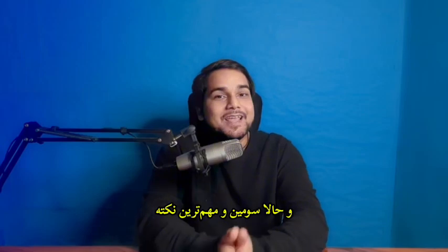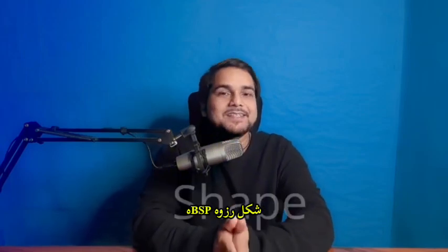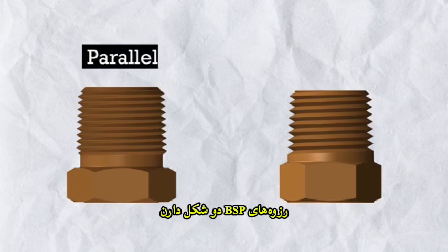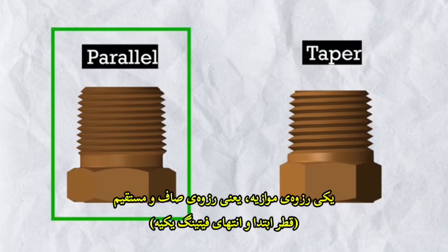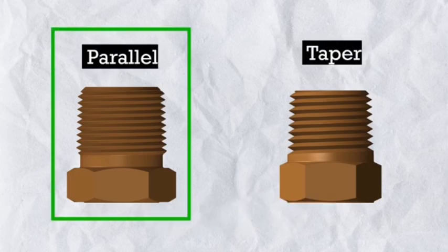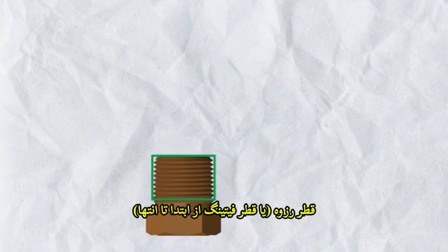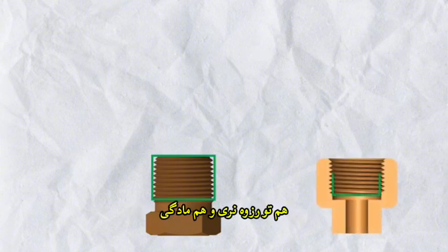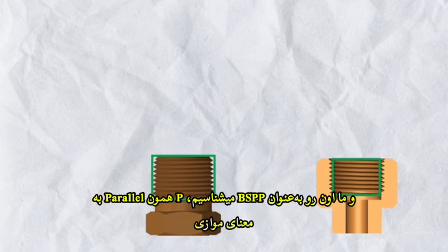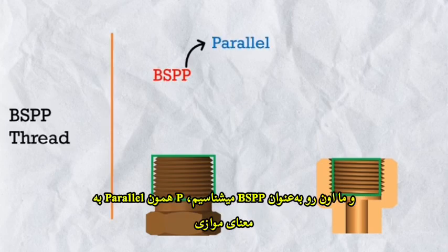And now the third and most important thing is the shape of BSP thread. BSP threads come in two shapes. One is parallel thread, means a straight thread. The diameter of the thread will stay constant throughout the length in both male and female thread, and we denote it as BSPP, P for parallel.